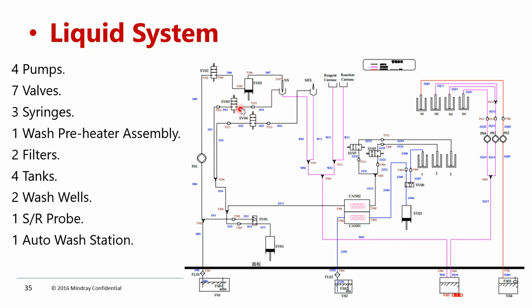So there is valve number 3 in this line. Whenever you are facing an issue where the wash station jet is not sufficient, or the pressure is not adequate, you have to check this line. Water is coming from the side, not from the bottom, right? So it is coming from the side and it will fall onto the probe. If that line pressure is not sufficient, you have to clean this line and this valve. Okay. And simultaneously this same line is also for mixer cleaning.